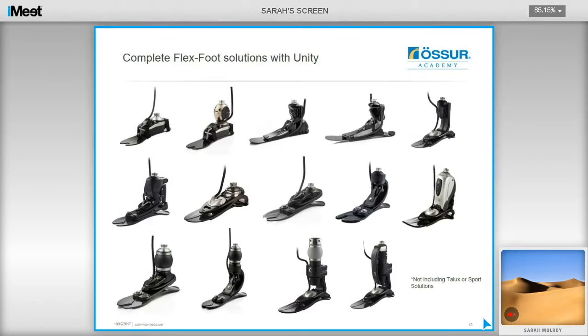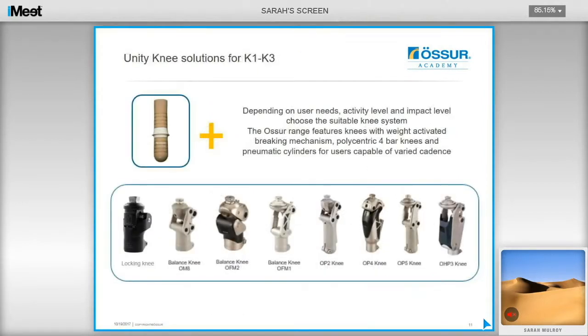The Unity-compatible prosthetic feet include low-active balance solutions, dynamic and impact feet, including the newly added ProFlex XC torsion and ProFlex LP torsion. It is only the Talix foot and sport solutions where Unity is currently not an option. For the trans-femoral Unity application, you need to assess the user's activity level and impact level to choose a suitable knee system. There is now a full range of knee solutions from K1 to K4, including knees with weight-activated braking mechanisms, polycentric four-bar knees, and pneumatic cylinders capable of varying walking speeds.